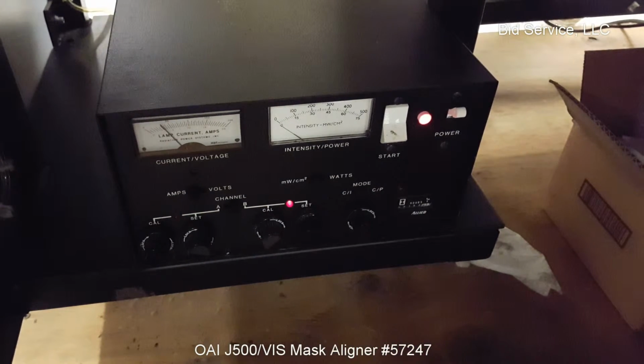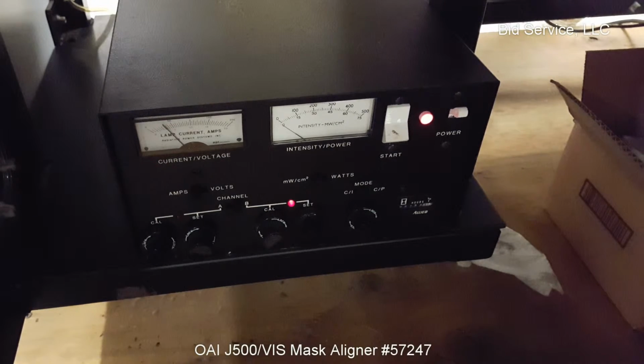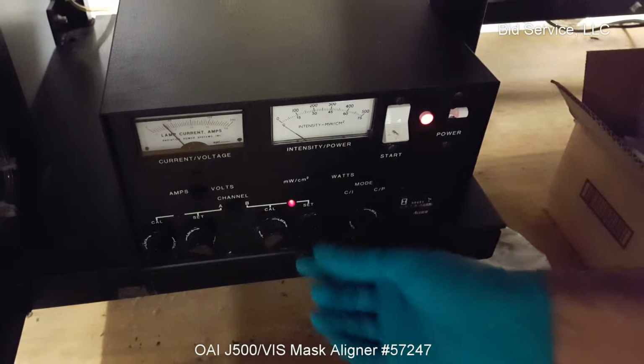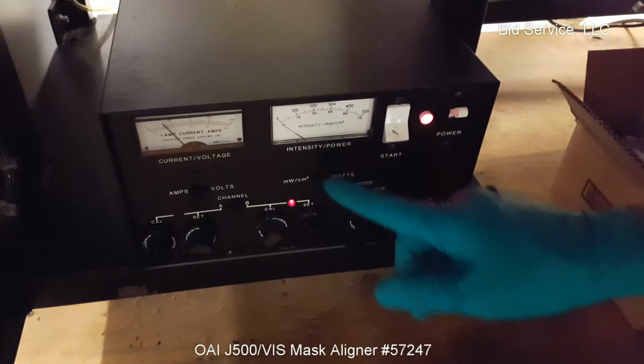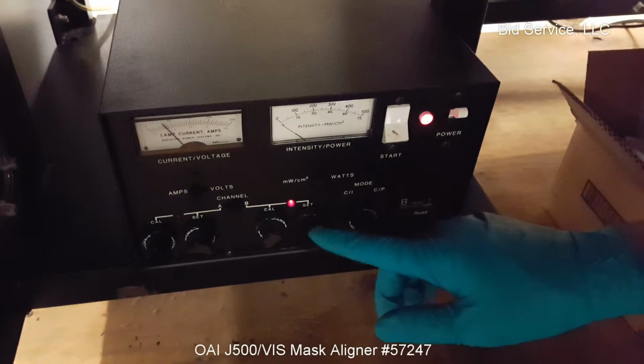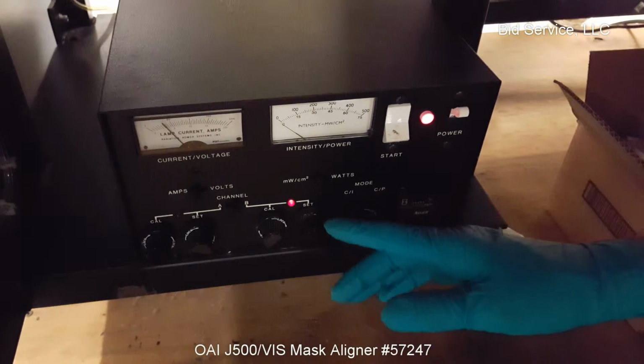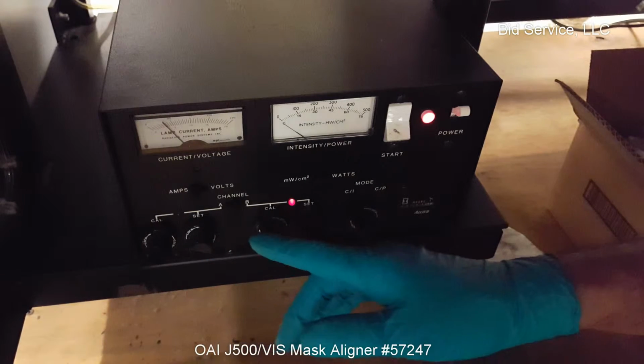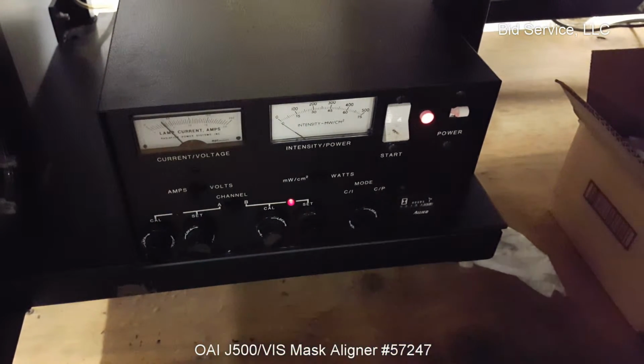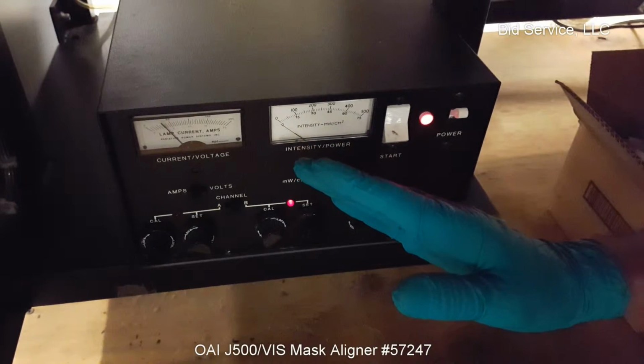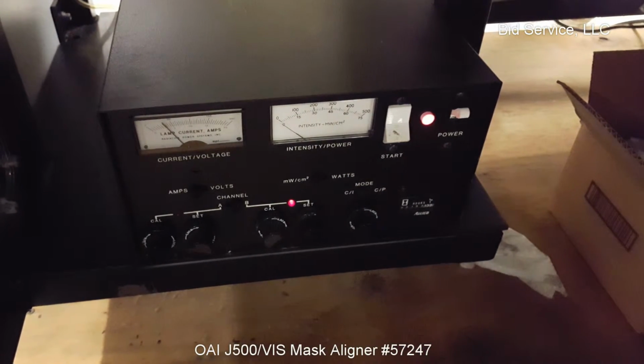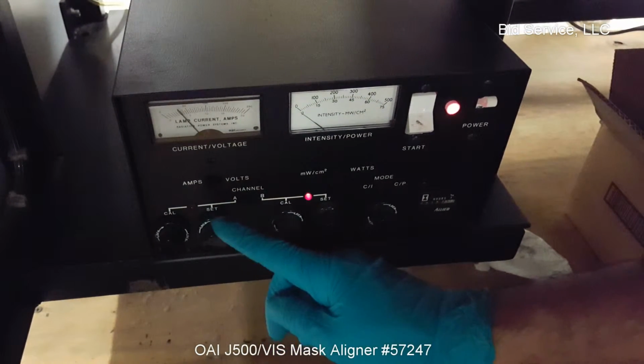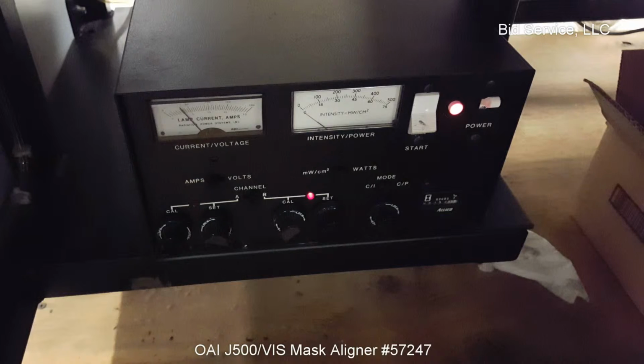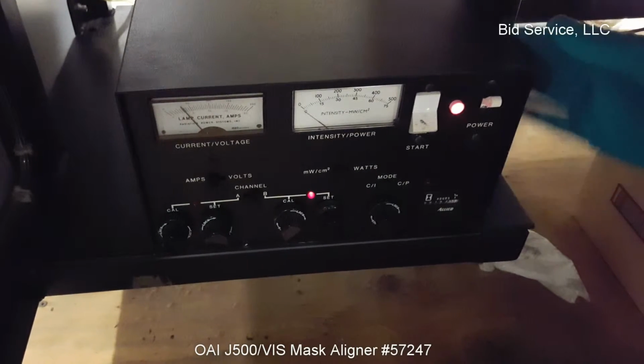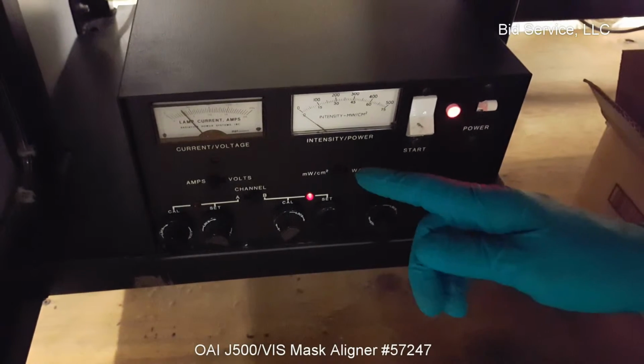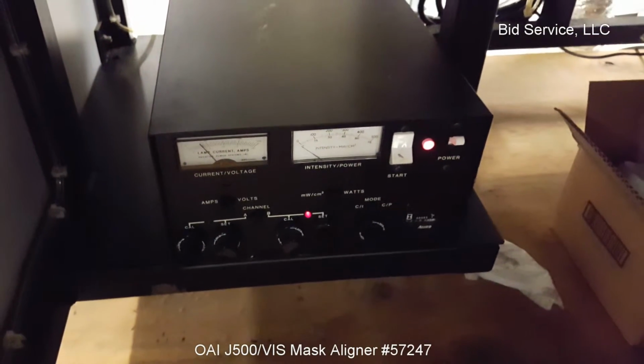Once the calibration is done at about 190 watts of lamp power, the set point can be used to set the intensity level of the UV radiation to the desired value. For example, if it is 10 milliwatt per centimeter square, by adjusting the set point we can increase it to 12 milliwatt per centimeter square, or decrease it to 8 milliwatt per centimeter square using the set point only, and that will help to reduce the power to the lamp using the intensity of the UV energy.